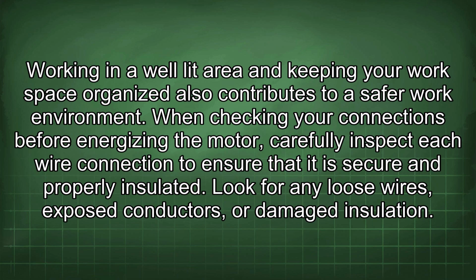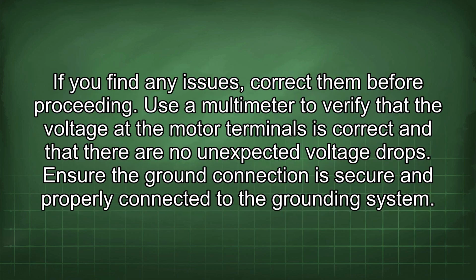When checking your connections before energizing the motor, carefully inspect each wire connection to ensure that it is secure and properly insulated. Look for any loose wires, exposed conductors, or damaged insulation. If you find any issues, correct them before proceeding. Use a multimeter to verify that the voltage at the motor terminals is correct and that there are no unexpected voltage drops. Ensure the ground connection is secure and properly connected to the grounding system.